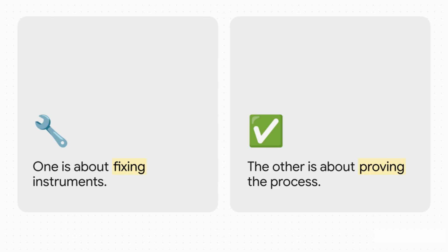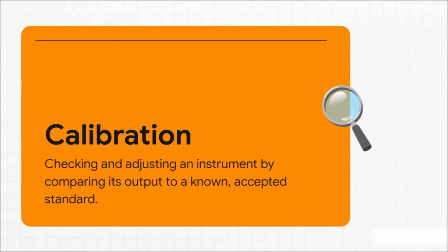One is about the tool, the other is about the final result of the whole system. So the key thing with calibration is that it focuses on one single piece of equipment. You take a pH meter, a thermometer, whatever it is, and you check its reading against a certified, known standard. If it's off, you tweak it and adjust it until it's dead on. This is what makes sure the data coming from that instrument is real and trustworthy.